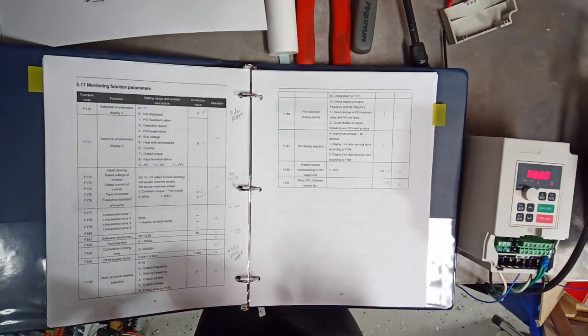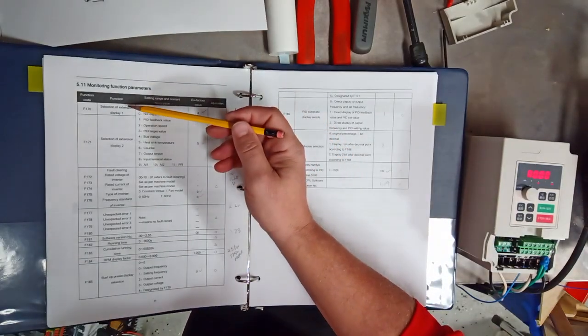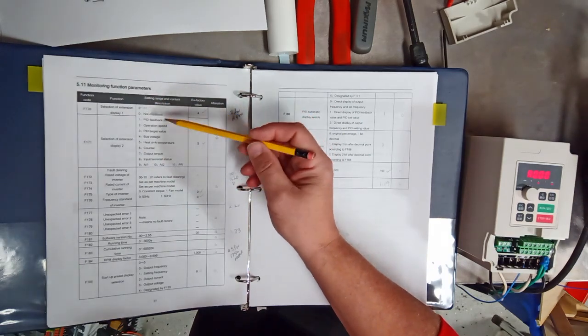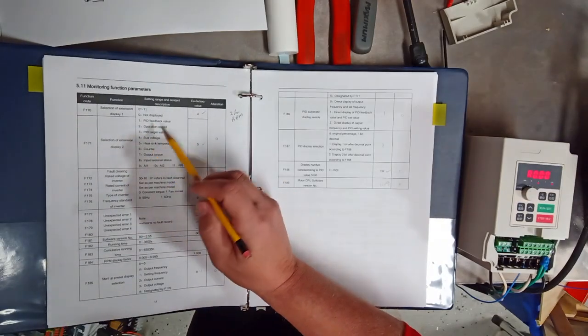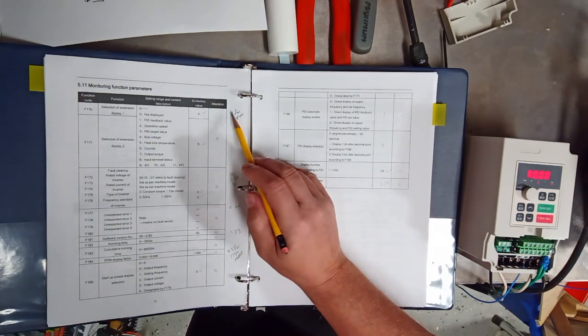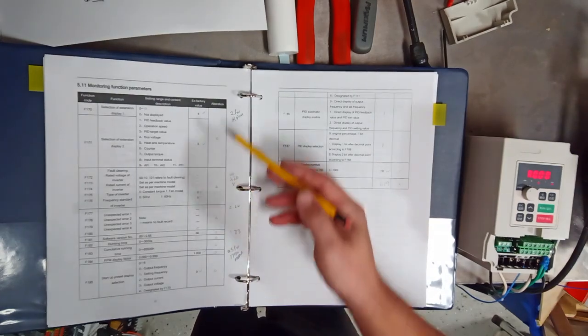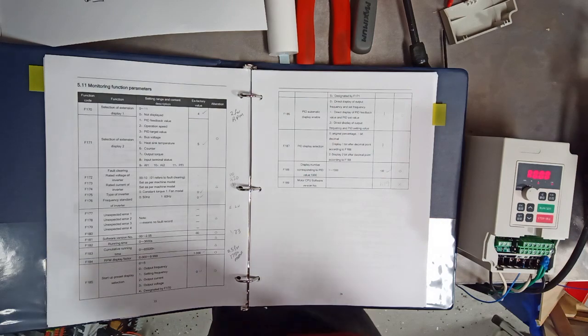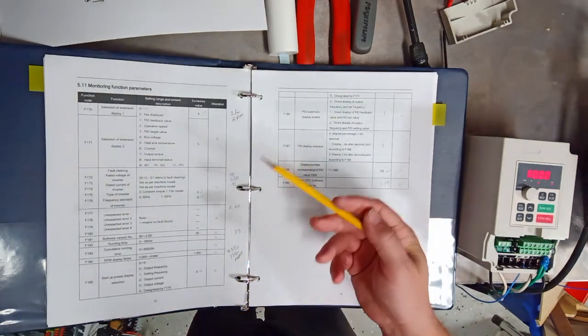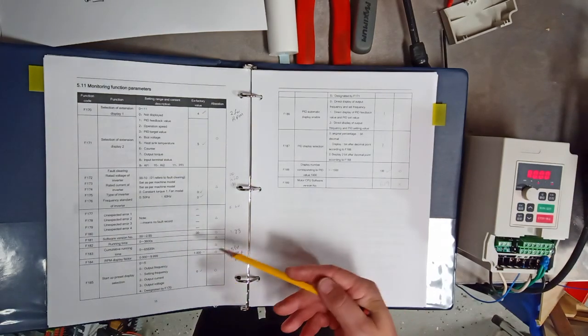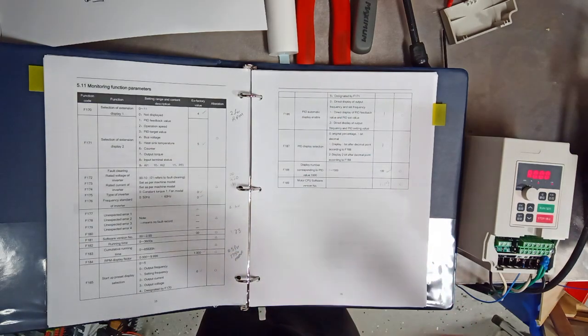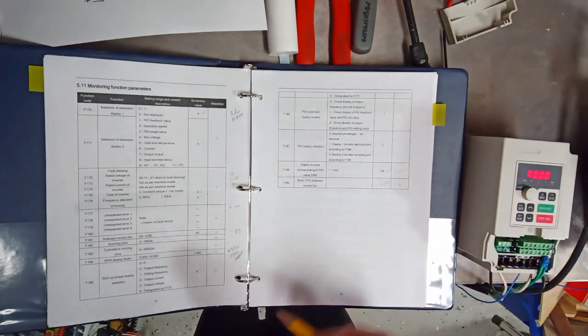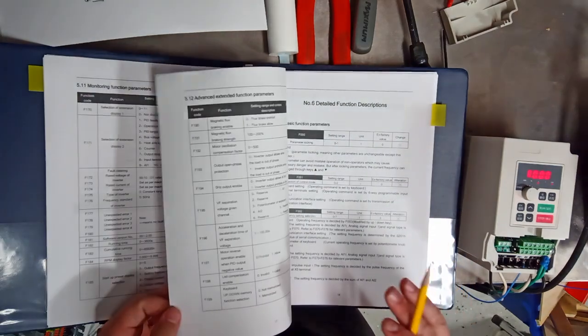Now, this is where we have to be able to make the change so we can see the RPM. So, the selection of extension display one, it was not showing me operational speed. So, I had to turn around. It was originally for bus voltage, but that's not right. So, I changed it to operational speed. So, I changed this to 2 and now I got RPM displayed and I had to come down to here at 184. If you're using 3600 RPM because it's by the number of poles, a two-pole motor will output, if it's 1.0, 3600 RPM. Because mine's 1750, I had to change this down to 0.5 to get the correct RPM being displayed for the frequency.